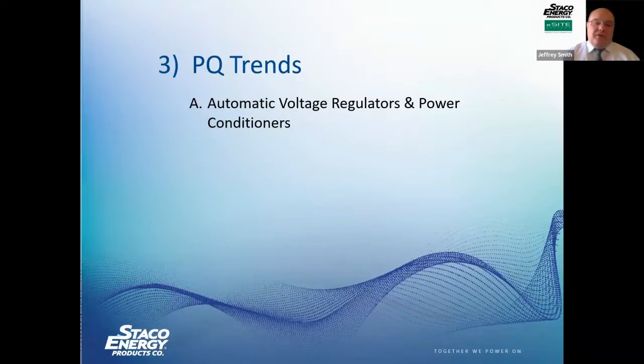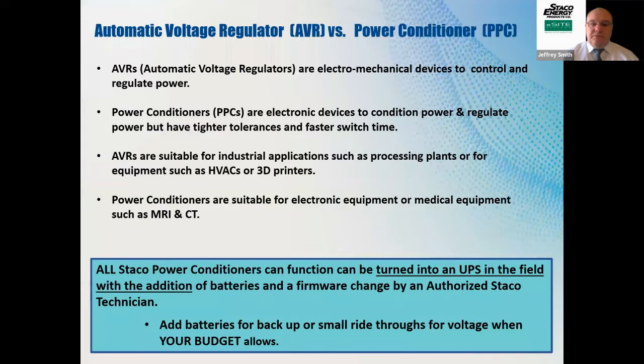Automatic voltage regulators and power conditioners. Next slide. In our Staco speak, we call it the AVR and the PPC. The AVR is a system with electromechanical devices, meaning that it takes a little bit of time to change the voltage up and down depending on what the systems are. Now the PPC is an electronic version, where if you have changes, there's an instant change to keep the output within the regulation of what we state, plus or minus 1 to 2%. So there's different types of things that you can look at for these systems.